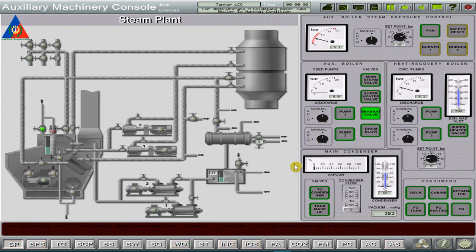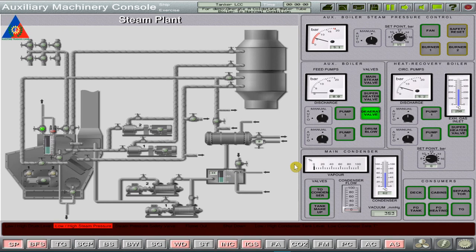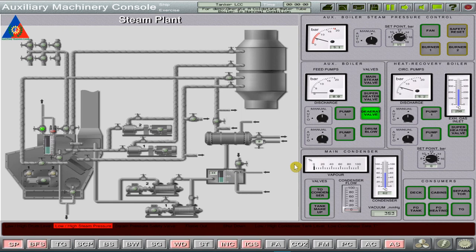The simulated steam plant system is intended to produce steam used in the turbo generator turbine, cargo pump turbines, and in the ship's technical and domestic heaters as a heating agent. The system can generate wet or saturated steam and superheated or dry steam. The wet steam consumers are used in the technical and domestic heaters on board ships, whereas the superheated steam is used for driving the turbo generator and cargo pump turbines.